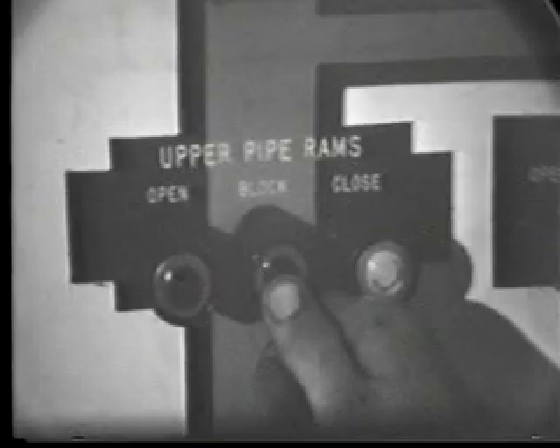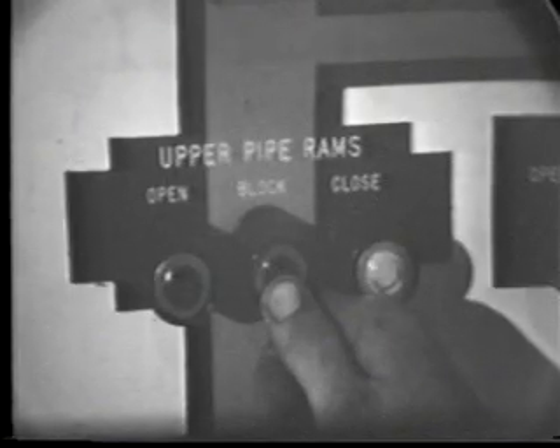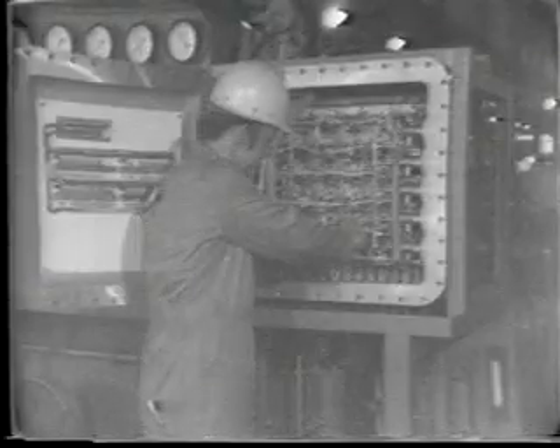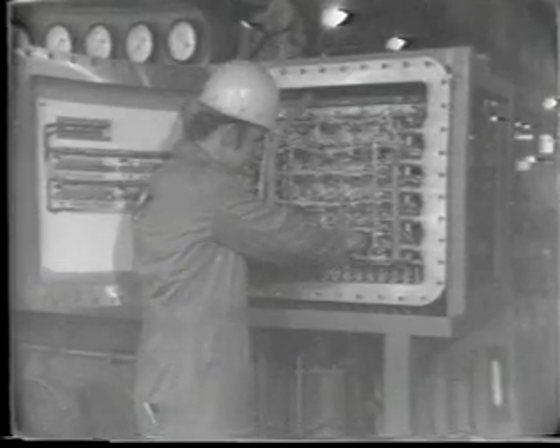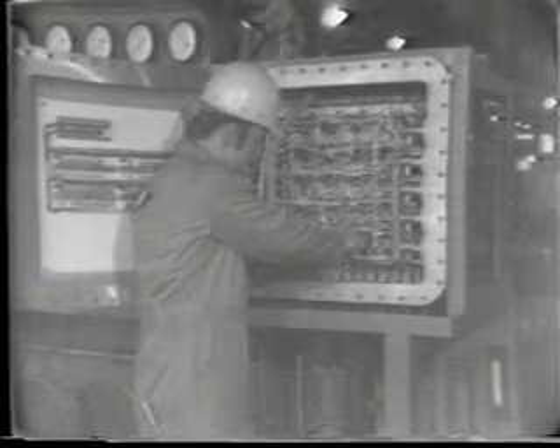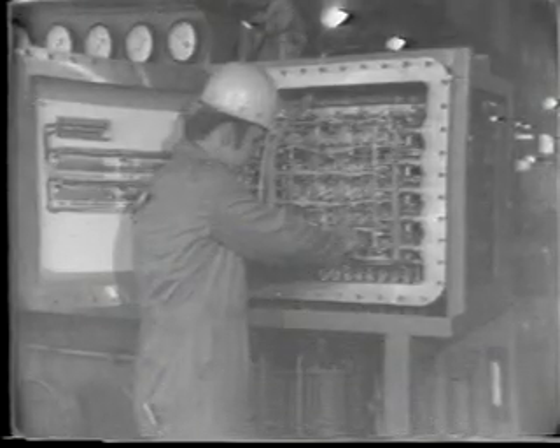When you press the block button, both function solenoids are energized at the same time in order to go into the block position. If one of the solenoids does not fire, then the function will not shift into block. It will remain in the same position or shift to the other position.